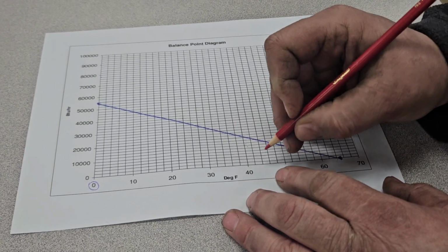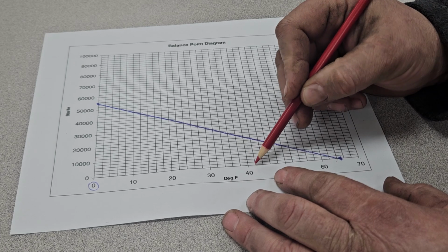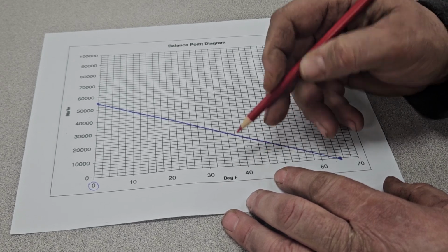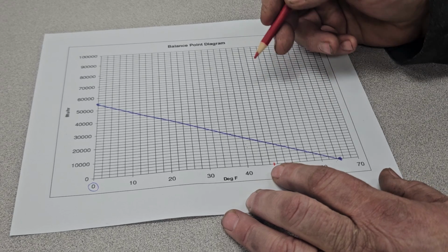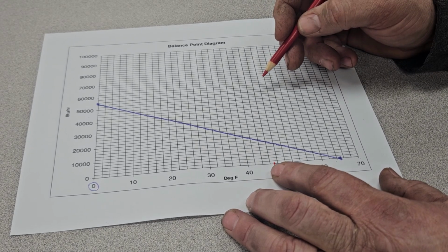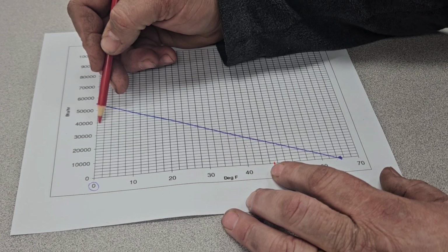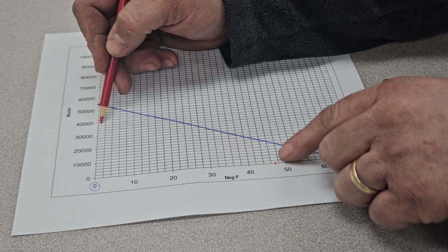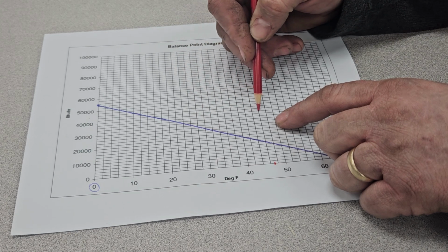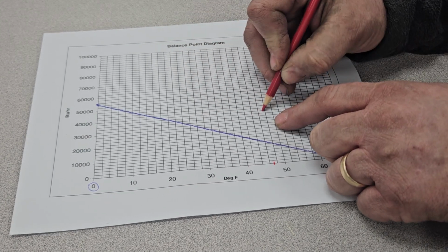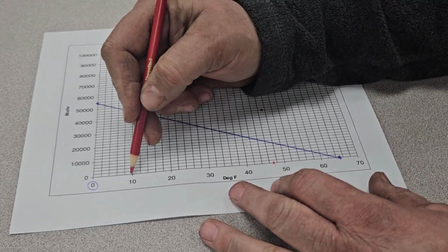So what we're going to say is at 47 degrees, so 40, 42, 44, 46, 47, at 47 degrees, that this particular heat pump is capable of producing 40,000 BTUs of heat. So at 40,000 BTUs of heat, we'll draw a line over until we hit 47 degrees, and that happens to be right there. And then AHRI comes out and says at 17 degrees.